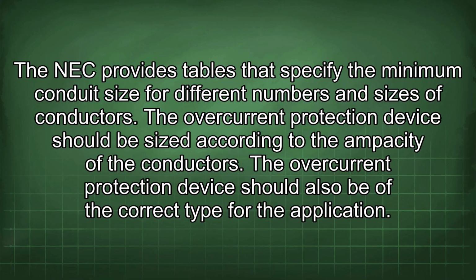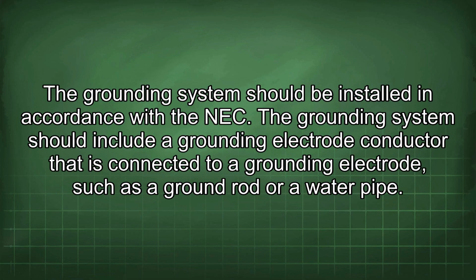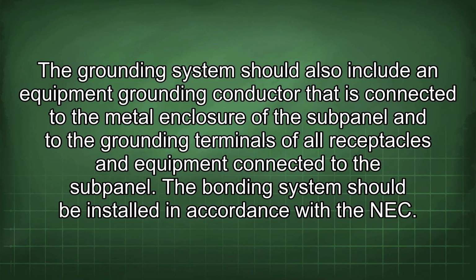The overcurrent protection device should be sized according to the ampacity of the conductors. The overcurrent protection device should also be of the correct type for the application. The grounding system should be installed in accordance with the NEC. The grounding system should include a grounding electrode conductor that is connected to a grounding electrode, such as a ground rod or a water pipe. The grounding system should also include an equipment grounding conductor that is connected to the metal enclosure of the subpanel and to the grounding terminals of all receptacles and equipment connected to the subpanel.